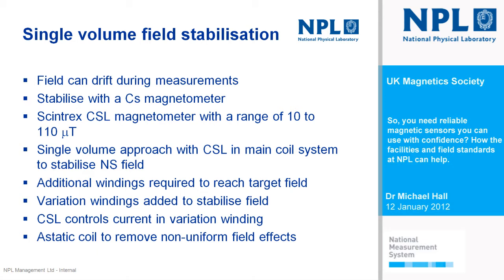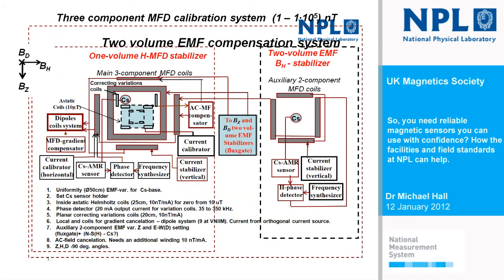This very busy slide here shows a kind of summary of different approaches that can be used, single volume and two volume. And really all I wanted to say about this particular slide is that we have a cesium magnetometer here inside of our 3-axis Helmholtz coil system, so that we don't suffer from the gradients that I've just described. Any gradient will be considerably smaller, and using an astatic coil we can compensate for that, plus any non-homogeneity of the field.